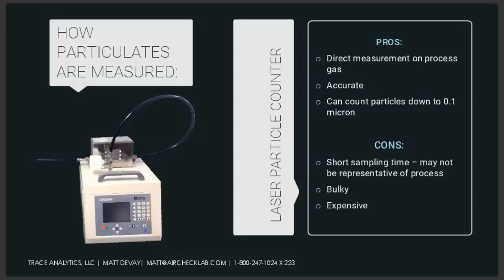They tend to have small sampling volumes, which kind of feeds into that. They're heavy, bulky, kind of a pain to move around and ship. They're normally used for ambient sampling, so you almost always need some kind of additional equipment to make it suitable for compressed air. And they are really expensive instruments. There's also some hidden cost of operation in that they require regular calibration. And that's something that people don't necessarily consider: what is it going to cost for me to ship this thing and get it calibrated on any kind of regular basis.